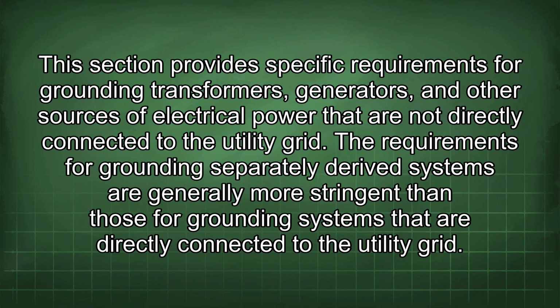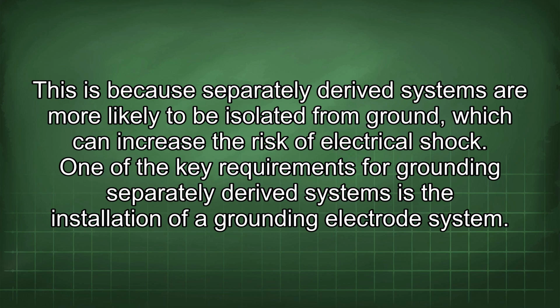This section provides specific requirements for grounding transformers, generators, and other sources of electrical power that are not directly connected to the utility grid. The requirements for grounding separately derived systems are generally more stringent than those for grounding systems that are directly connected to the utility grid. This is because separately derived systems are more likely to be isolated from ground, which can increase the risk of electrical shock.